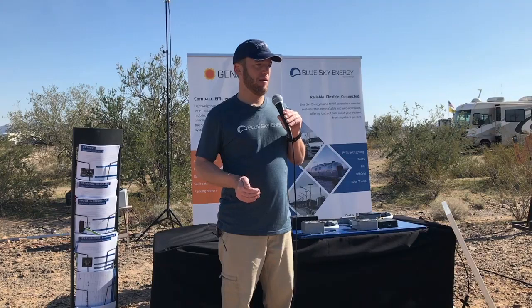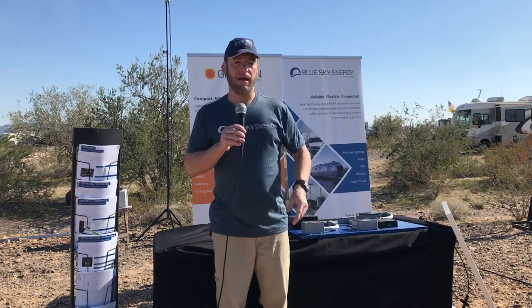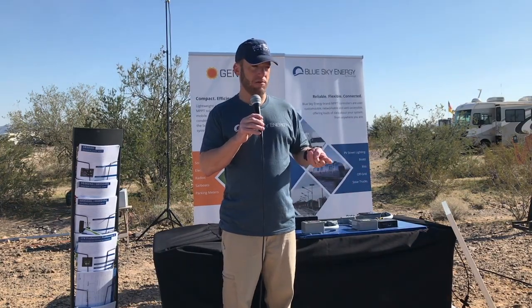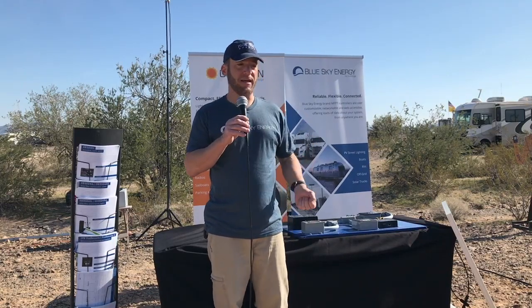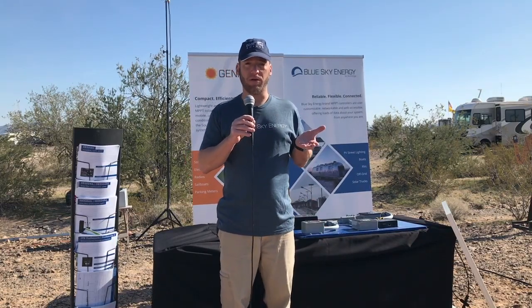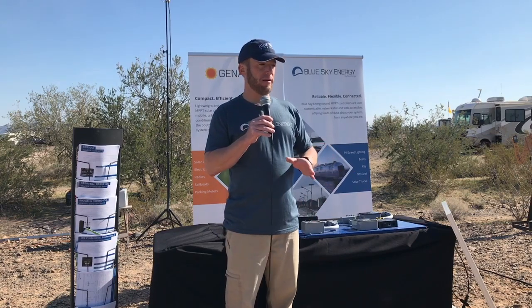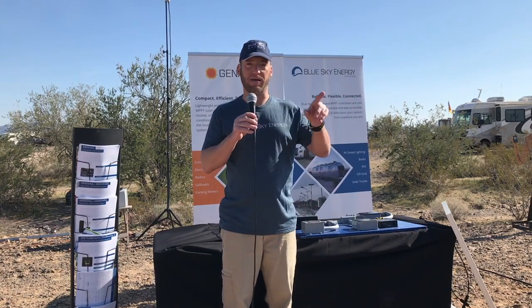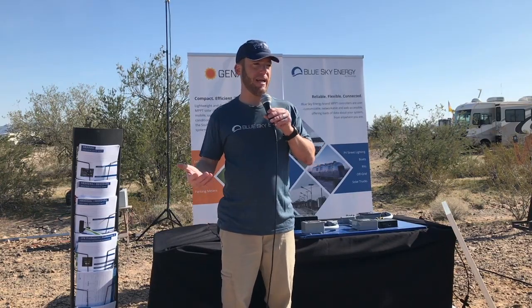Can I have multiple charge sources on the same battery bank at the same time? The answer is yes, absolutely. Specifically, all batteries, even your car, all battery chargers, even the alternator, basically have 2 modes: constant current (bulk mode), where it gives everything it's got trying to raise your battery's voltage, or constant voltage (CV). That's what you see as CC/CV - constant current, constant voltage. Constant voltage is where you're providing enough current to maintain a voltage.